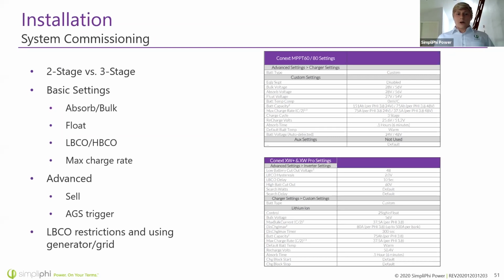3-stage charging means you're adding on the float stage—bulk, absorb, and then float as the 3rd stage. That's great for when you have a PV system, for example. If you've got a DC source that would otherwise go to waste, you might as well use it to float the batteries. They're not going to mind—it keeps them nice and full.